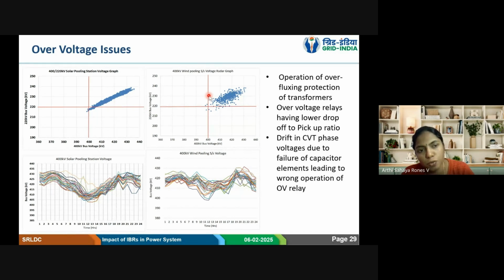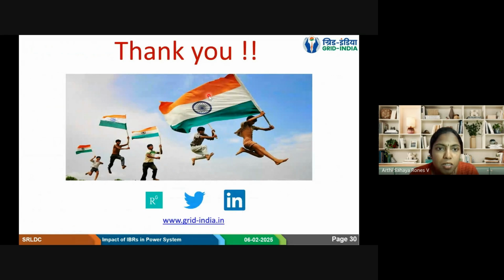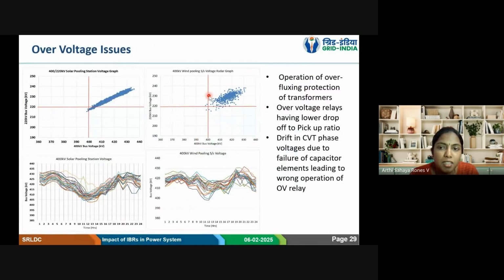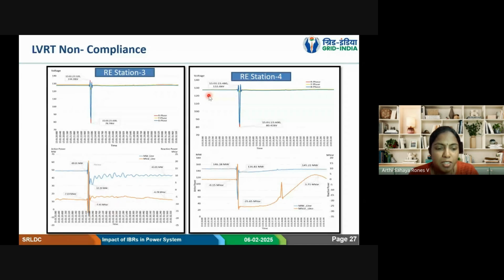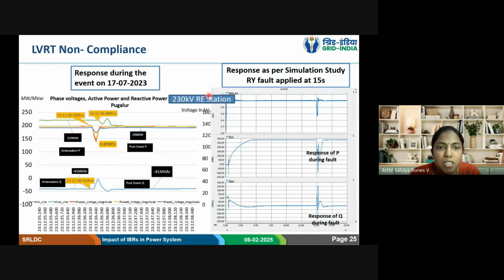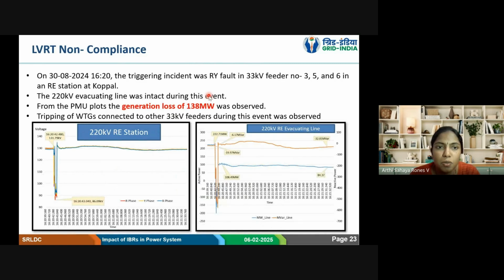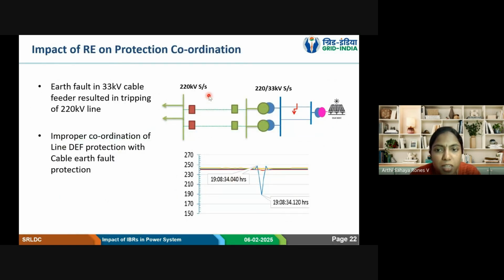Another reason for over voltage related maloperation is the CVT drift. Actually, over voltage may not be there, but because of drift in the CVT, one of the phases may read a slightly higher voltage, and that particular phase will trigger the over voltage protection operation, and due to that we may lose the line. Those are some of the maloperations related to over voltage issues. In general, I have tried to quickly cover the major protection challenges that we encounter in the grid due to the REs.